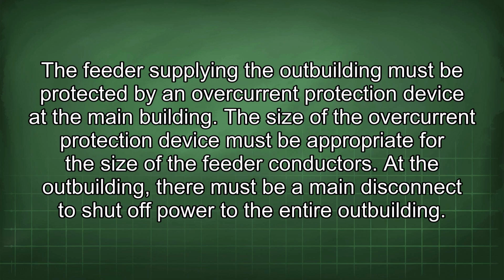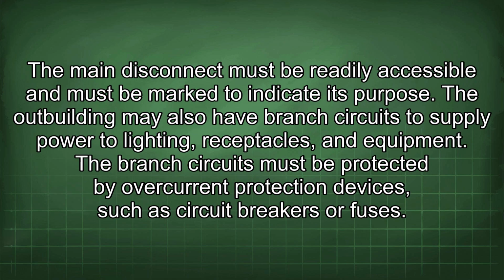The feeder supplying the outbuilding must be protected by an overcurrent protection device at the main building. The size of the overcurrent protection device must be appropriate for the size of the feeder conductors. At the outbuilding, there must be a main disconnect to shut off power to the entire outbuilding. The main disconnect must be readily accessible and must be marked to indicate its purpose.